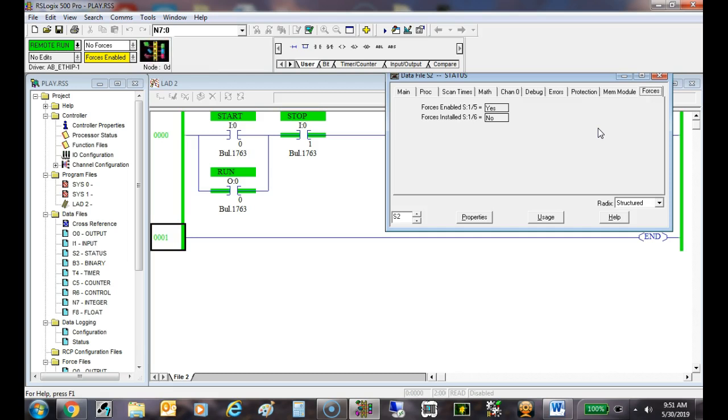So we do that a lot when we're developing programs and we don't have it hooked up, or we want to force something. But guys, when you force outputs, you got to be extremely careful, and you got to understand the consequences of the force, because what's happened is you've taken away all the safety features that's built into those programs. All these sensors, monitoring the sensors, monitoring if somebody's present, you've taken that away. And you could literally kill somebody by forcing an output, right? Did I tell you about the US Steel guy?